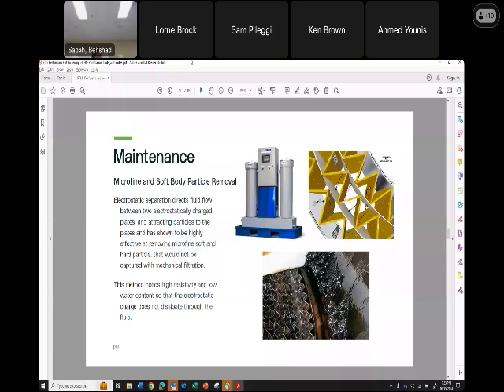The picture down below on the right, that's not from Pickering, that's from another station. That looks very bad. We've examined our elements after several months of operation, and they looked fairly clean. There were some deposits. I've taken those deposits and looked at them under a microscope, and found all the deposits were varnish, and there was no evidence whatsoever of carbon.